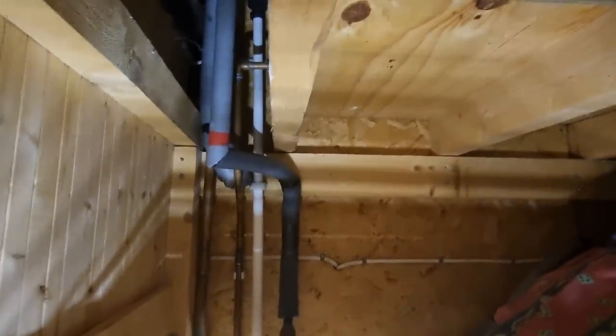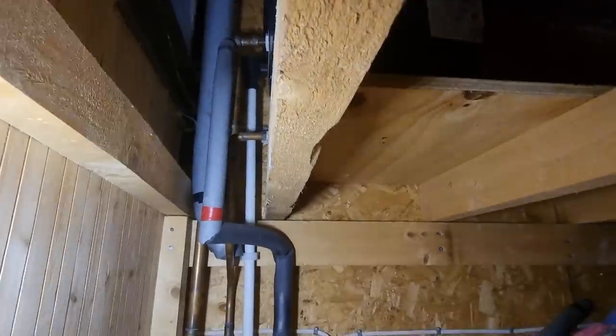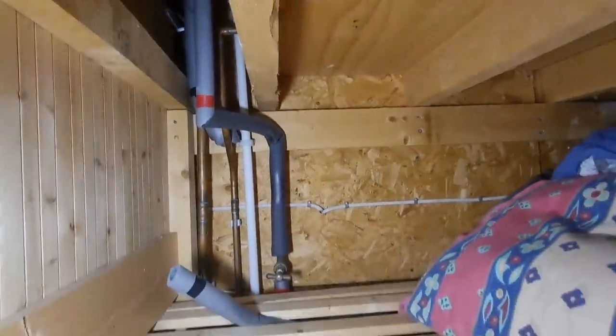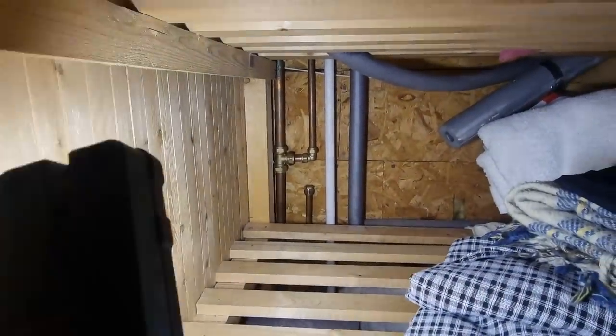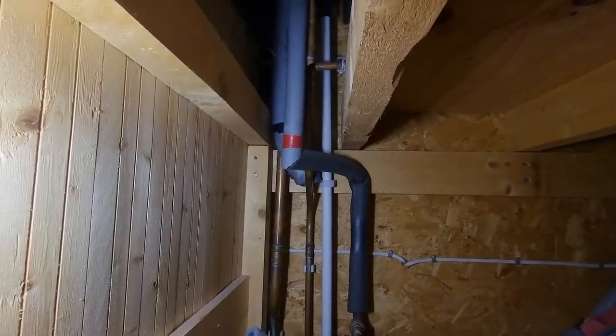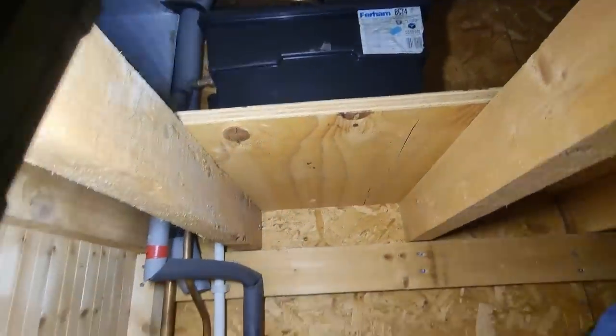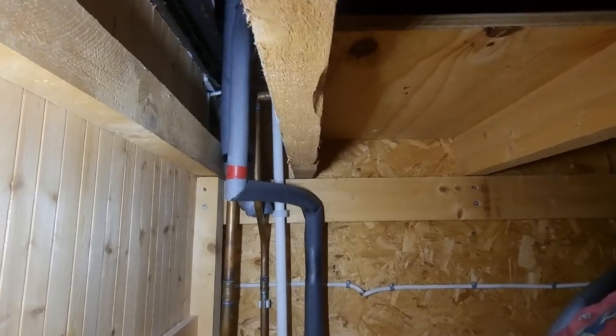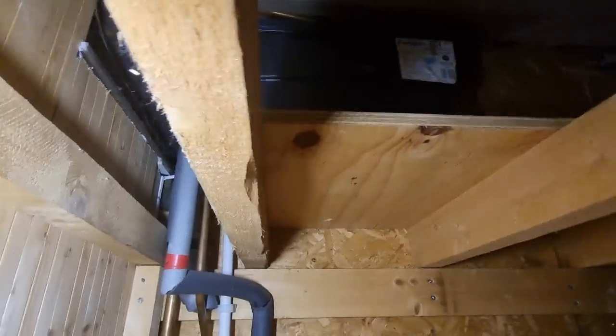Right, it's a bit of a weird layout, this house. It's like a dormer bungalow, but the header tank's up there. Follow the cold feed down. It's that one that's got some scale on it. Drops down, and it's been teed into the vent. Obviously, that cold feed has blocked. God knows where it runs. But in theory, it's either been blocked or it's been pumping over, one of the two. The vent, they've lifted the vent really high, which is normally a sign that it's been pumping over.